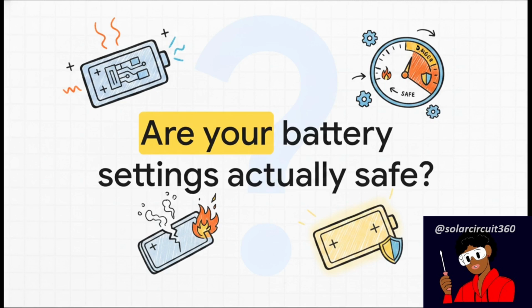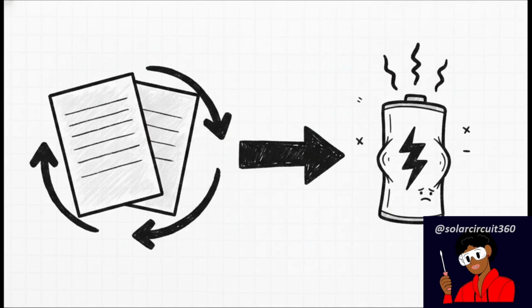We aren't here to just copy-paste someone else's homework. We need to know exactly what each parameter does and why it matters. Think about it. A BMS configuration that runs perfectly on one setup might be literally disastrous for yours. Why? Because cell chemistry, capacity, max discharge ratings, and specific manufacturer limits vary wildly from battery to battery. If you just slap a configuration from a totally different setup onto yours, you're rolling the dice. We're talking premature aging, cells swelling up like balloons, severe overheating, random system shutdowns, and totally permanent hardware failure.